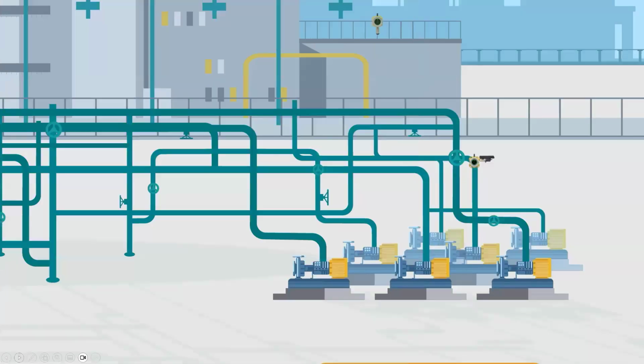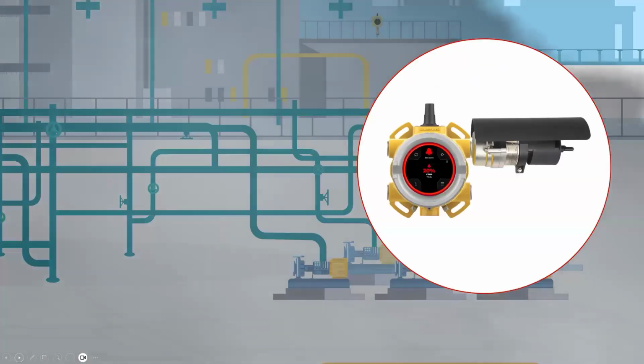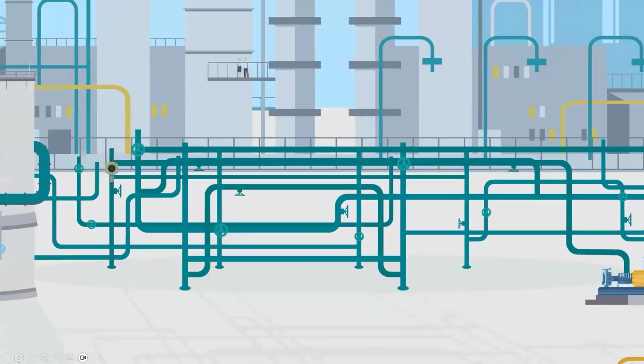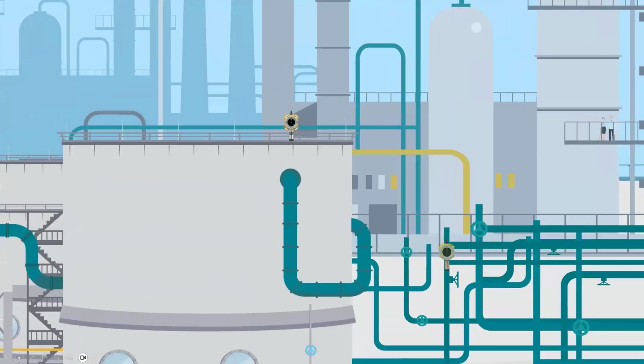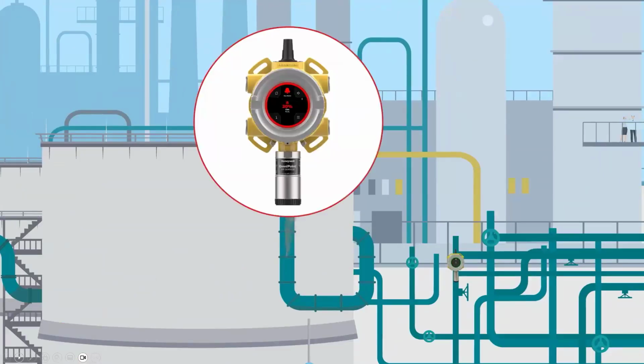A chemical plant manufacturing plastics uses hydrocarbon gases, such as ethylene, as an intermediate. An OmniPoint equipped with an Optima Plus would detect any excess ethylene present and activate an alarm. In many industrial facilities, storage tanks present a hazard from potential leaks. Dangerous levels of combustible gases like methane can leak from valves and entry points. An XP sensor configured with a catalytic bead sensor and connected to the OmniPoint will detect any rise in LEL levels in these high-risk areas and activate an alarm to alert workers of the hazard.